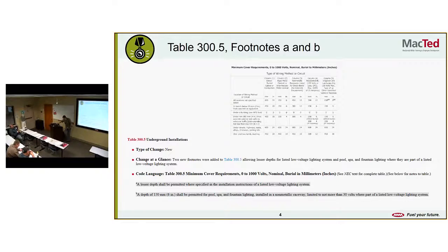They had a new change to underground installations. Two new footnotes were added to table 300.5, allowing lesser depths for listed low voltage lighting systems, and pool, spa, and fountain lighting, where they are part of a listed low voltage lighting assembly.